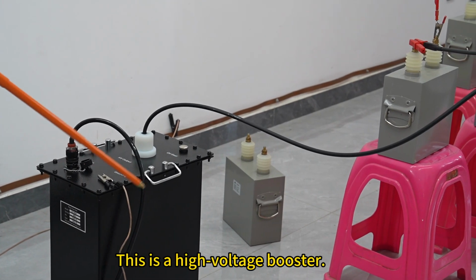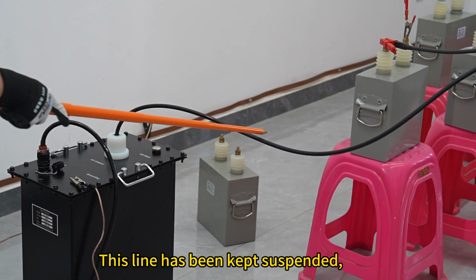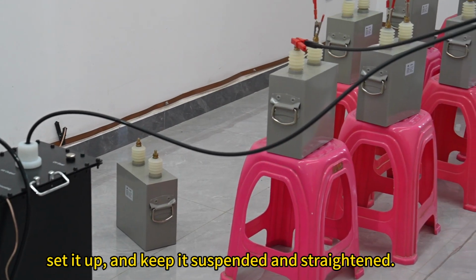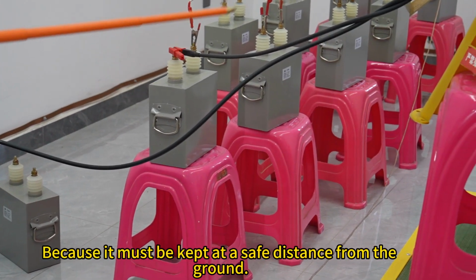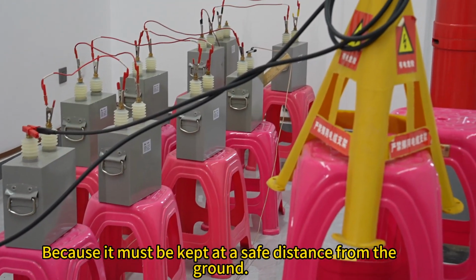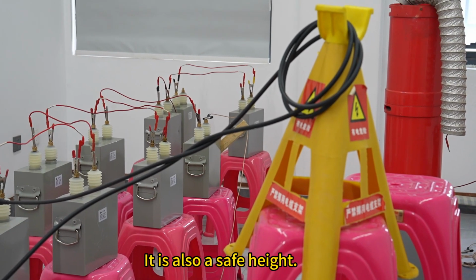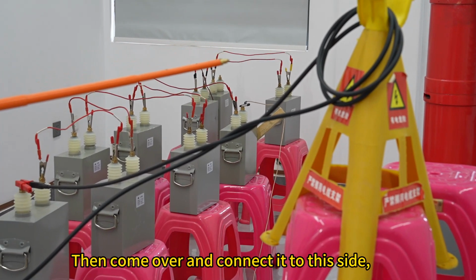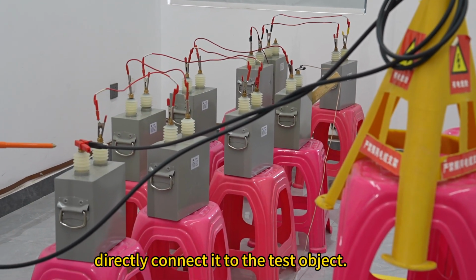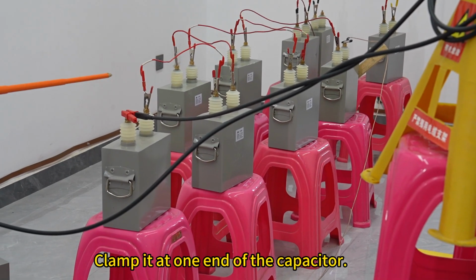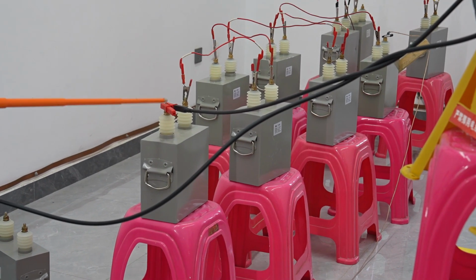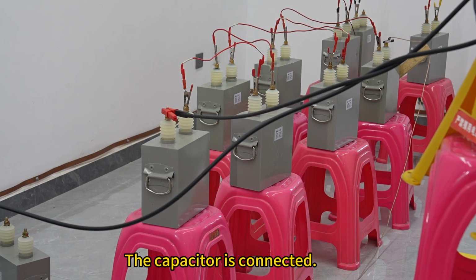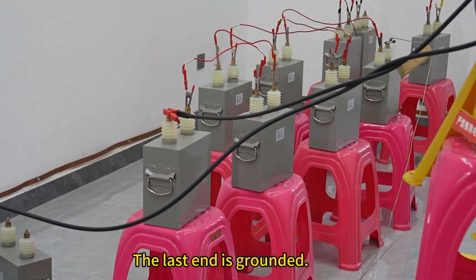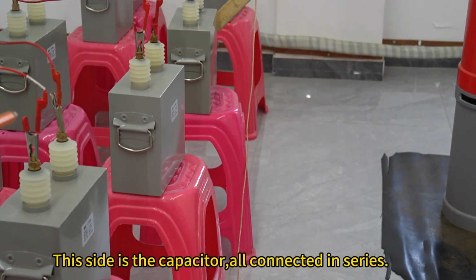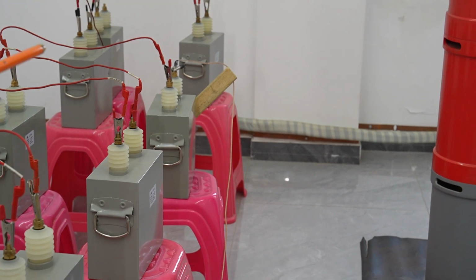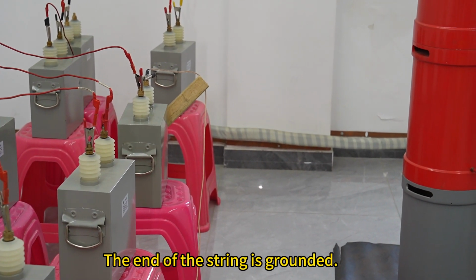This is a high-voltage booster. This line has been kept suspended, set it up, and keep it suspended and straightened. Because it must be kept at a safe distance from the ground. It is also a safe height. Then come over and connect it to this side, directly connect it to the test object. Clamp it at one end of the capacitor. The capacitor is connected. The last end is grounded. This side is the capacitor, all connected in series. The end of the string is grounded.